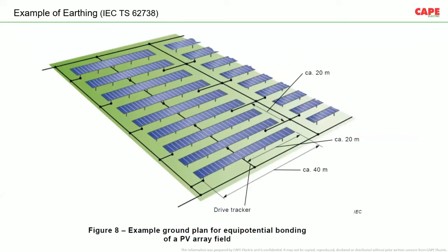For example, this one is from the standard IEC TS 62738. The standard says at least at every 20 meter you are supposed to have an interconnection. That means you are supposed to make a grid of, let's say, for example, 40 meter, and at least at 20 meter you are supposed to have a connection. But the size of the grid shall be made based on the soil resistivity. You have to analyze the soil resistivity, and there are certain calculations, and then you have to find out the size of the grid, and the frequency of interconnection must be made.